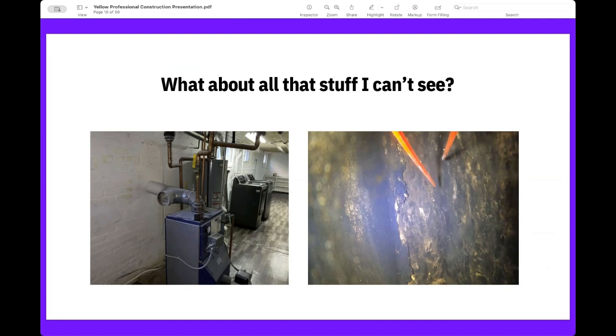Zero clearance or low clearance is construction language for a factory built fireplace unit that has to be installed exactly how the instructions say. Because yes, you can actually take clearances down to 1 to 3 inches if you do it exactly how the instructions say. So if we get up into the attic and I haven't put the fire breaks between the floors and I don't have the collar that keeps the insulation off the metal pipe, I'm inviting that fire, and it will happen eventually.